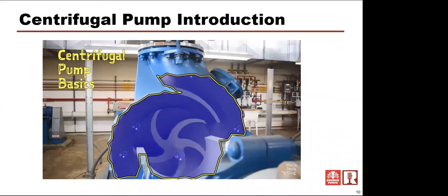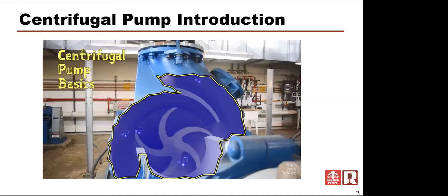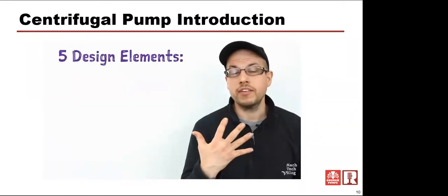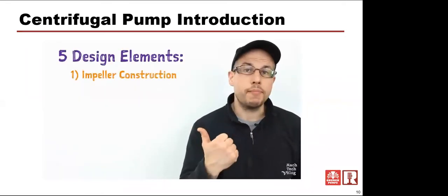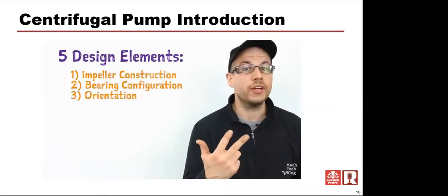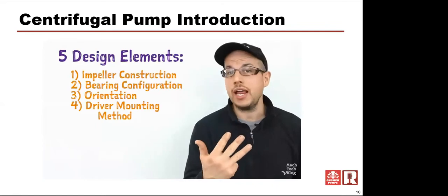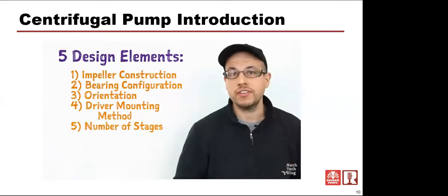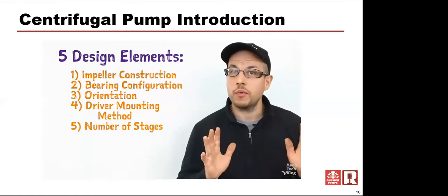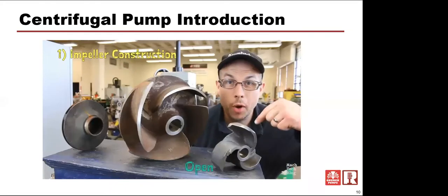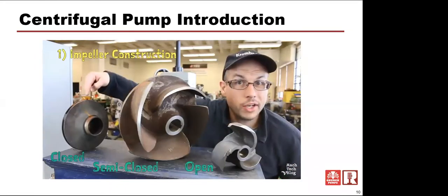All centrifugal pumps share this basic operating principle, but there are a few possible variations among them. There are 5 primary design elements to consider: impeller construction, bearing configuration, orientation, driver mounting method, and the number of stages. There are a few special designs as well, but those will have to wait for their own videos. There are 3 types of impeller: open, semi-closed, and closed.